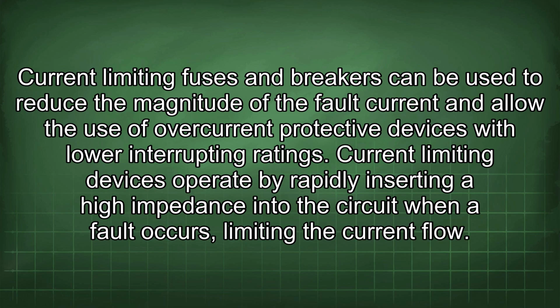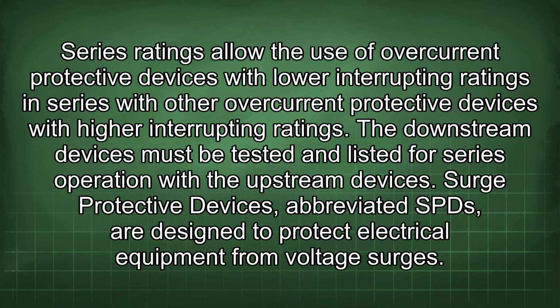Current limiting fuses and breakers can be used to reduce the magnitude of the fault current and allow the use of overcurrent protective devices with lower interrupting ratings. Current limiting devices operate by rapidly inserting a high impedance into the circuit when a fault occurs, limiting the current flow. Series ratings allow the use of overcurrent protective devices with lower interrupting ratings in series with other overcurrent protective devices with higher interrupting ratings. The downstream devices must be tested and listed for series operation with the upstream devices.